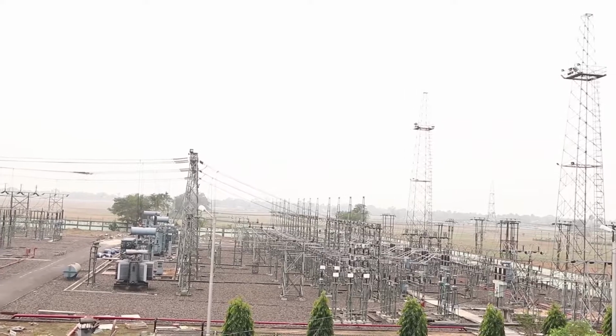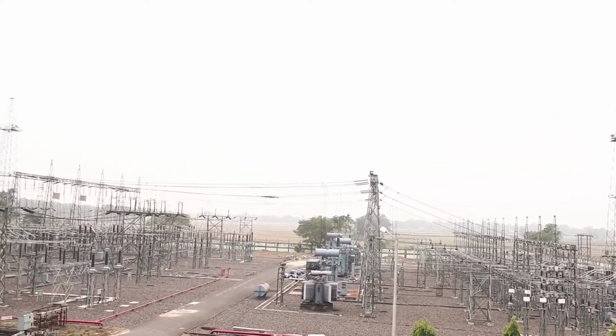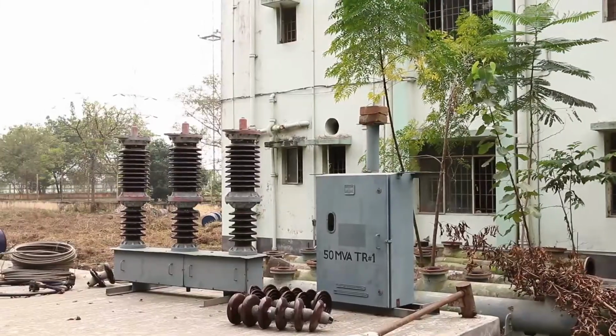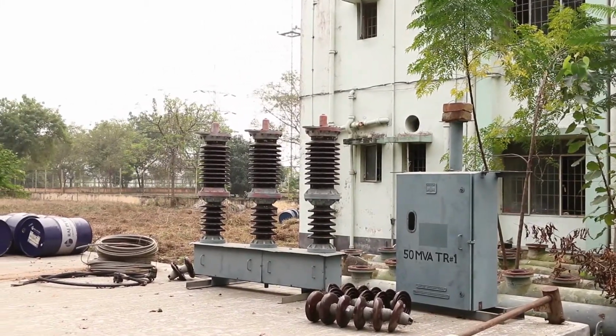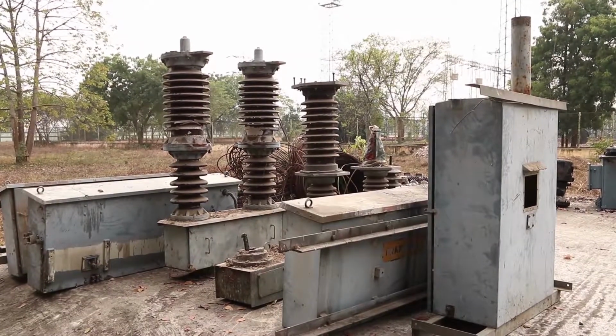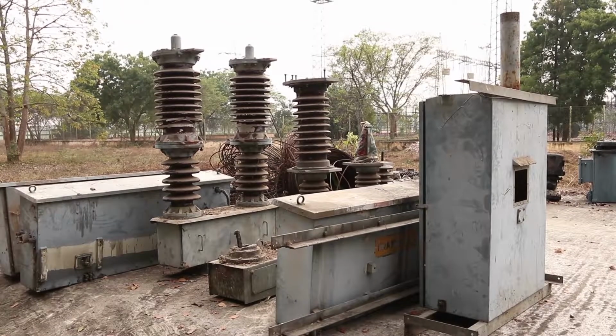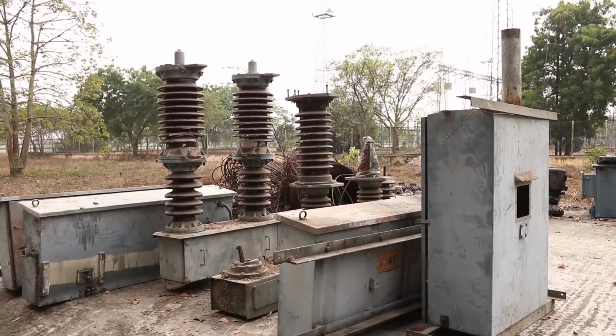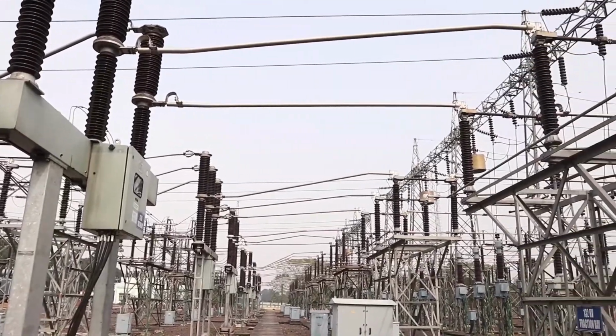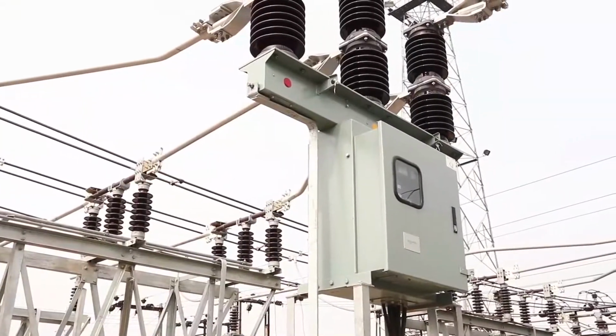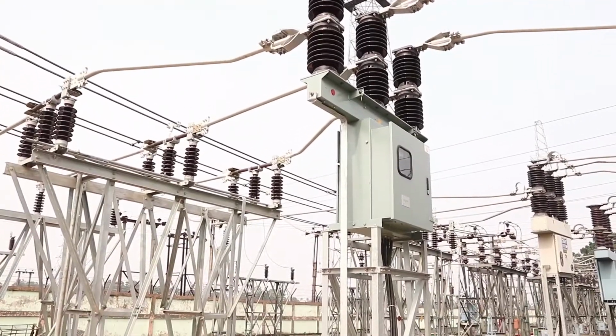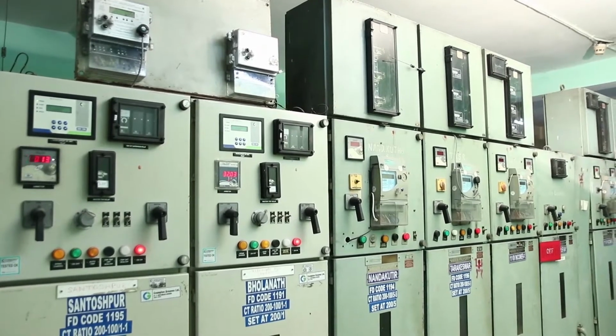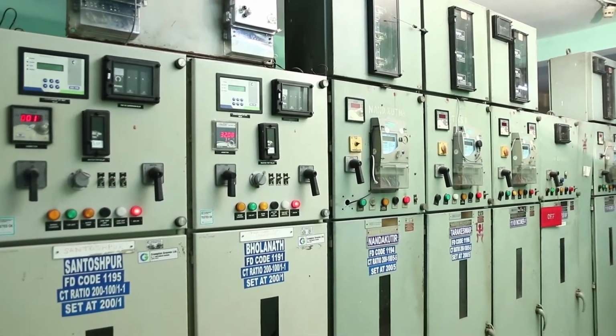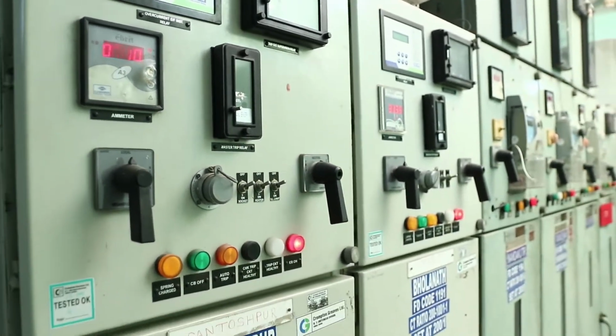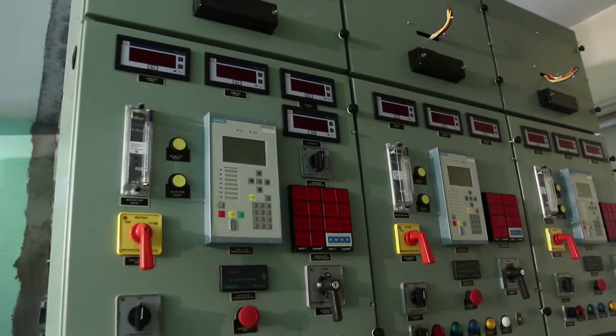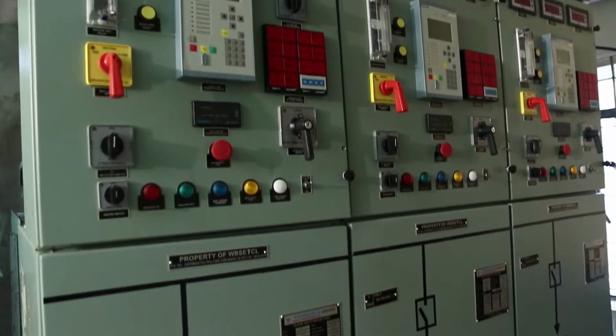This substation is almost 17 years old and old equipment has crossed its natural life. As a result, old equipment is being phased out. Old generation 132 kV SF6 hydraulic circuit breakers and 33 kV vacuum circuit breakers have already been replaced by new generation 132 kV SF6 circuit breakers and 33 kV vacuum circuit breakers respectively. Age-old 11 kV CGL oil circuit breakers are converted to vacuum circuit breakers. The whole 11 kV switchgear is going to be replaced by new Jamuna make 11 kV switchgear. This work has already started.